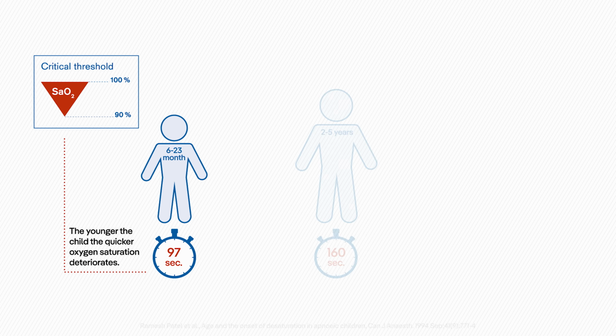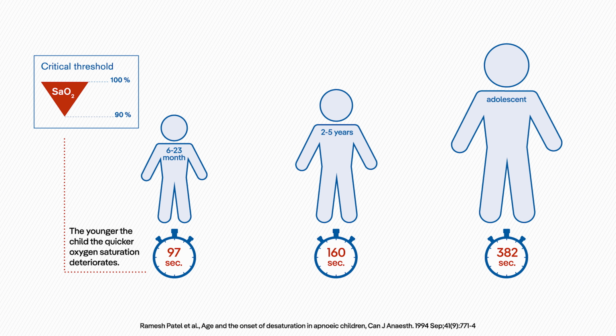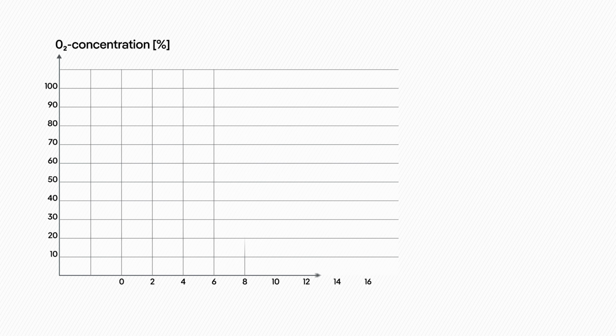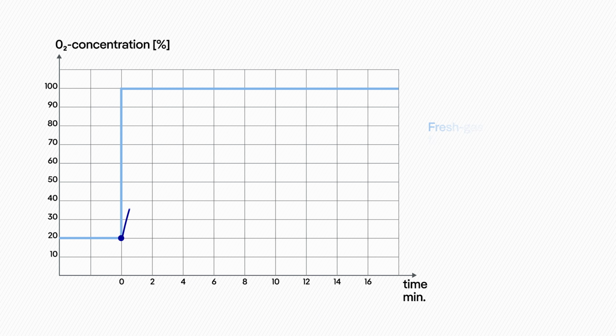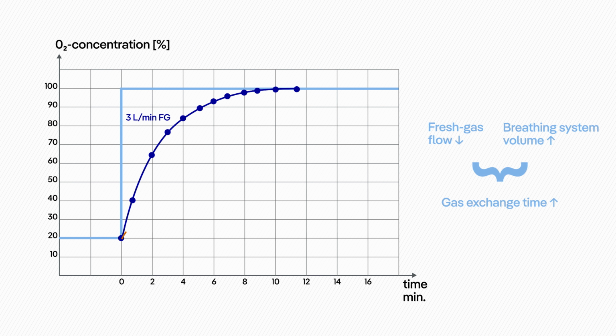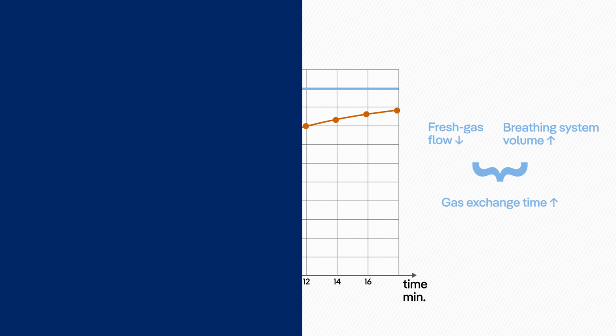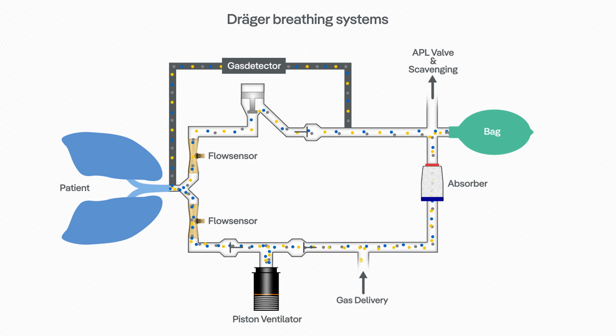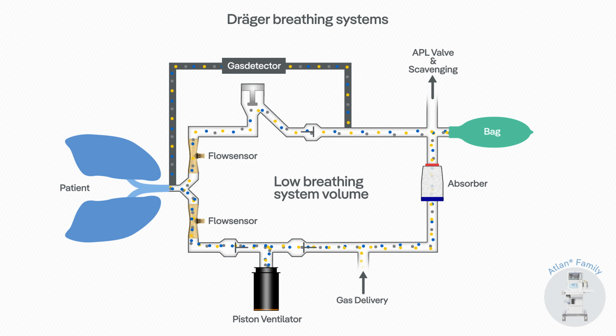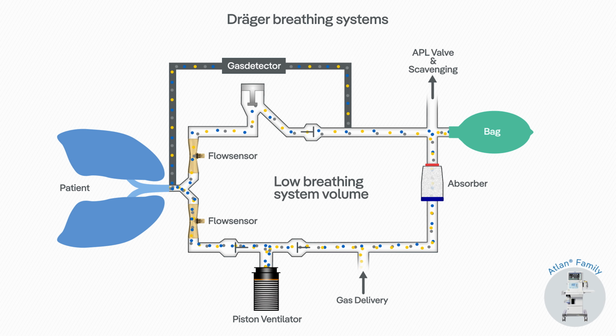During general anesthesia of pediatric patients, a quick change in gas composition can be crucial in order to counteract oxygen desaturation and improve oxygenation rapidly. The anesthesia device has to be designed accordingly to deliver the gas composition changes quickly to the patient. The breathing system volume and the fresh gas flow rate have significant influence on the reaction time. The higher the breathing system volume and the lower the fresh gas flow, the longer the time constant. The Dräger Atlan family anesthesia machines are designed for low breathing system volumes with short time constants.